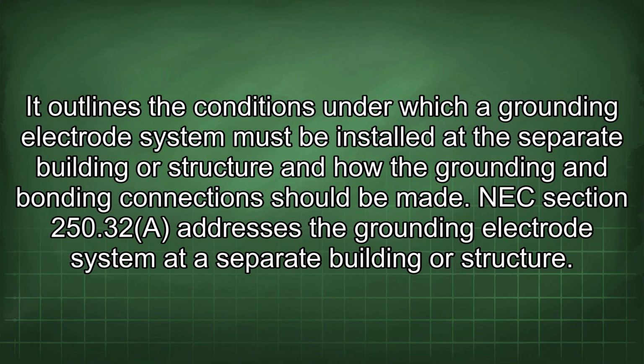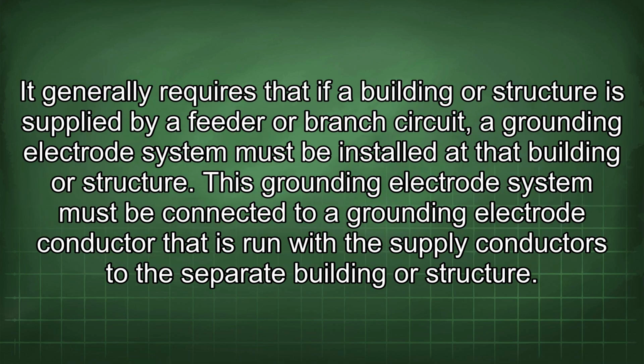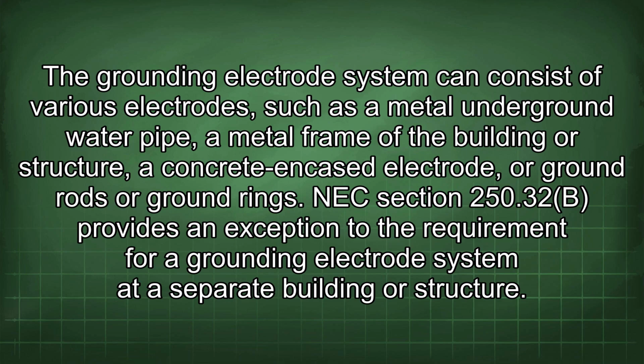NEC Section 250.32 addresses the grounding electrode system at a separate building or structure. It generally requires that if a building or structure is supplied by a feeder or branch circuit, a grounding electrode system must be installed at that building or structure. This grounding electrode system must be connected to a grounding electrode conductor that is run with the supply conductors to the separate building or structure. The grounding electrode system can consist of various electrodes, such as a metal underground water pipe, a metal frame of the building or structure, a concrete encased electrode, or ground rods or ground rings.